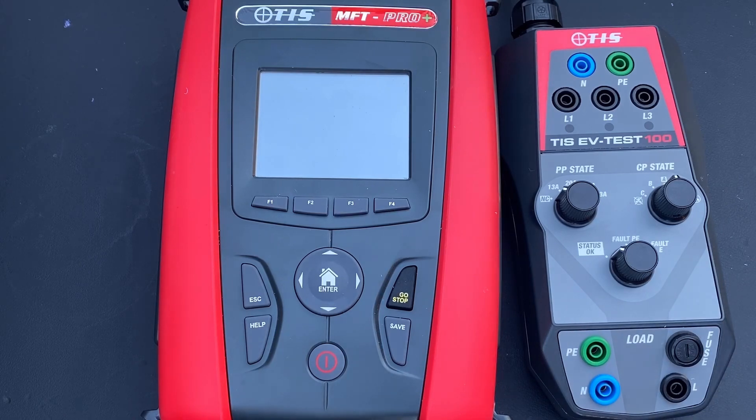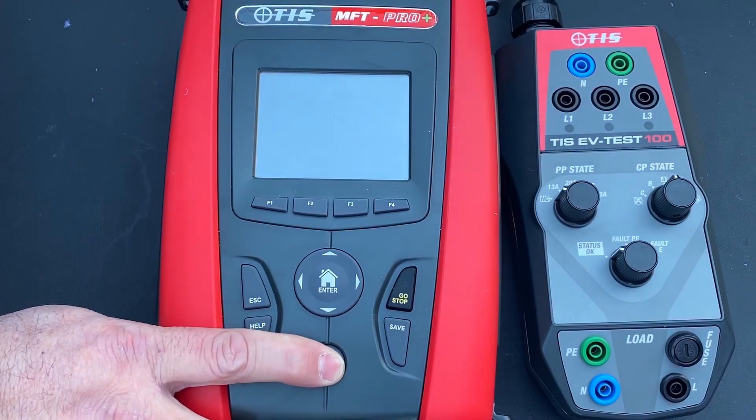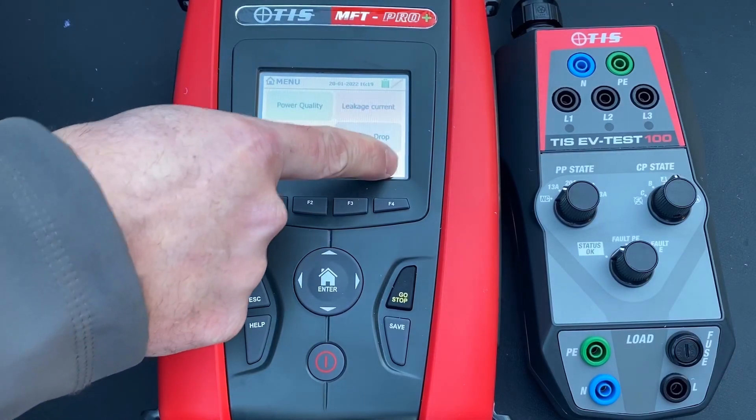We're going to turn the instrument on — this is our TIS MFT Pro. Would it be the same on the Pro Plus? The Pro won't do a three and four-wire earth electrode test; other than that, the MFT Pro and Pro Plus are exactly the same. We don't need that test for this, so if you're watching with the Pro and not the Pro Plus, this will also help you.